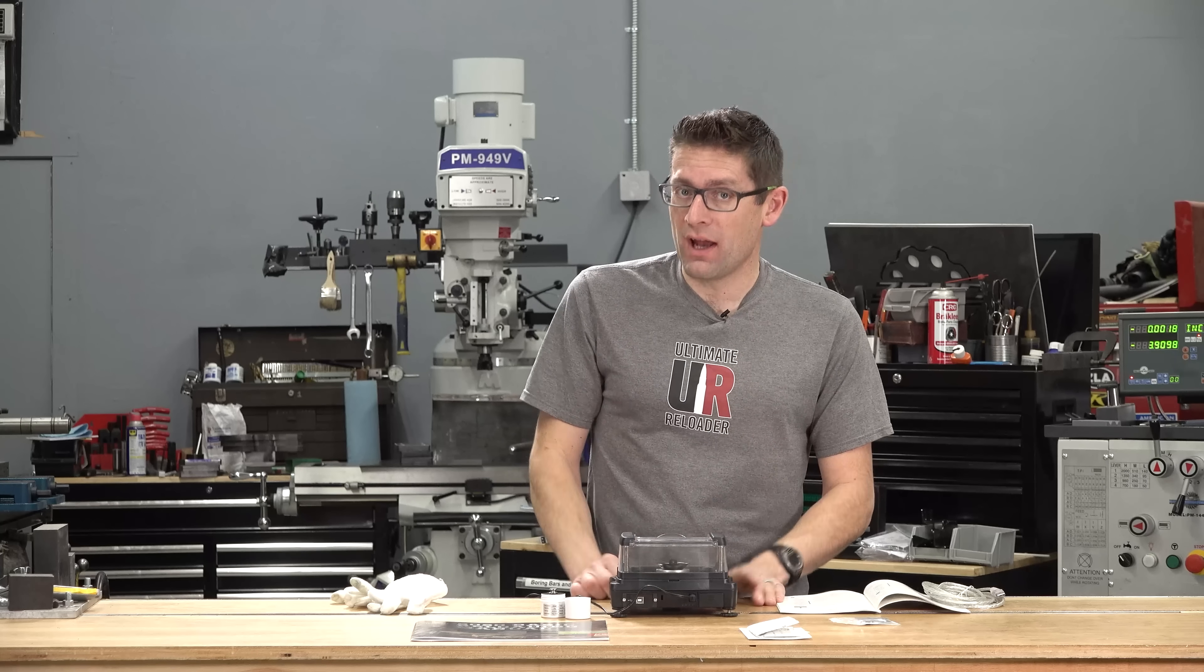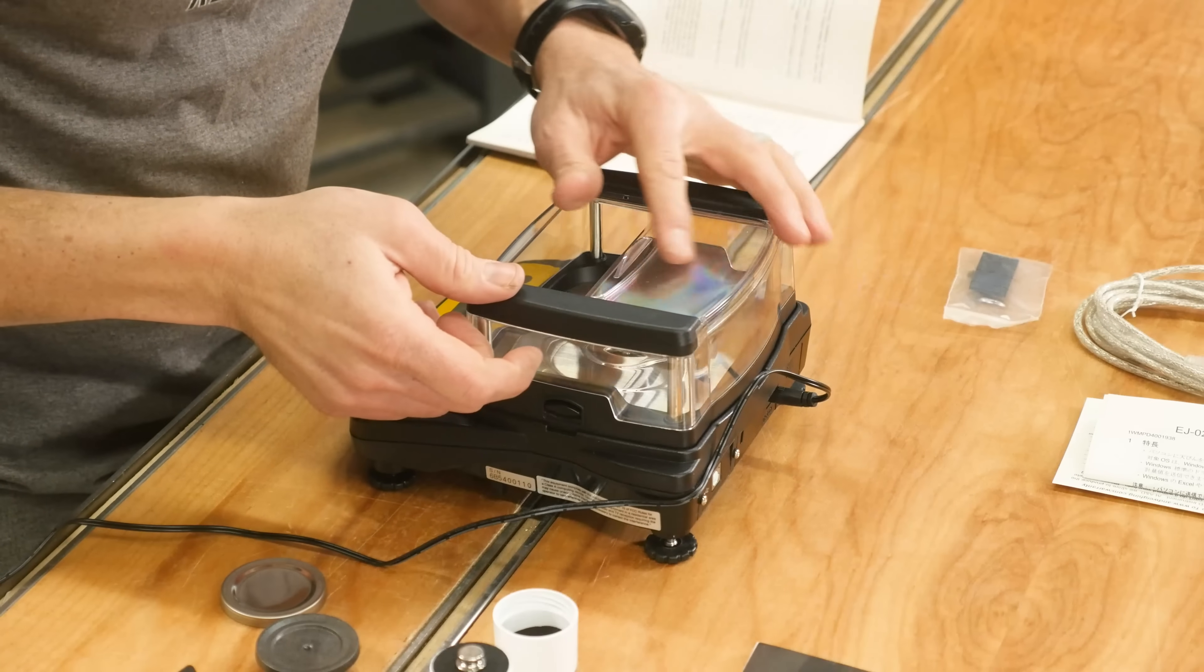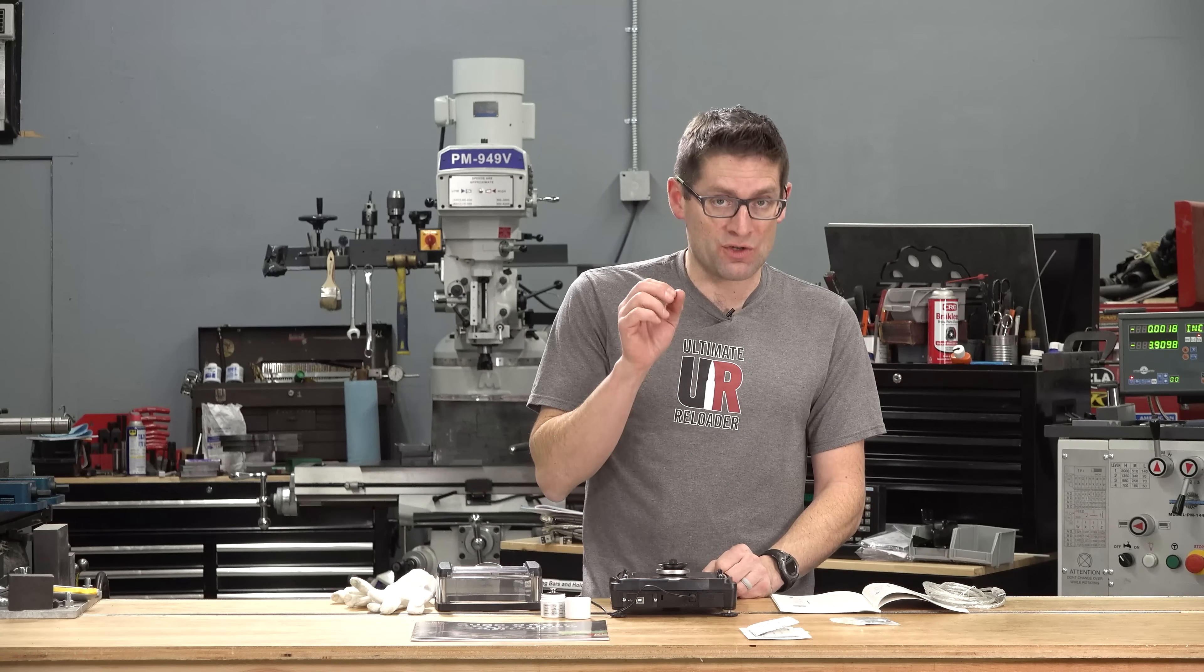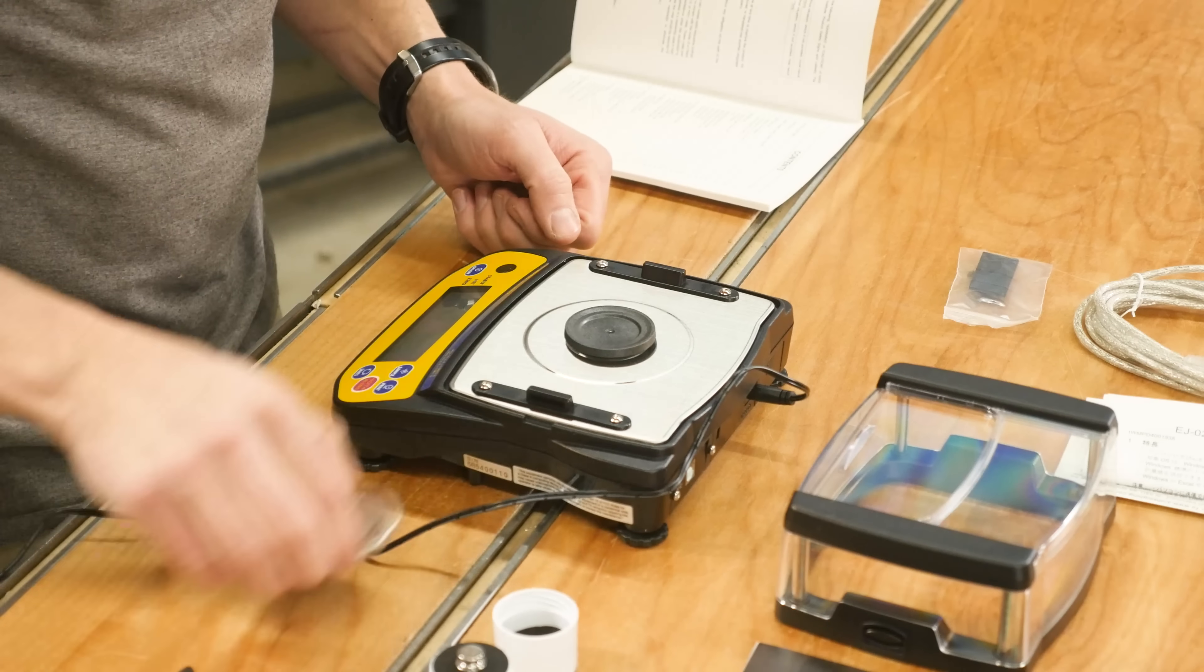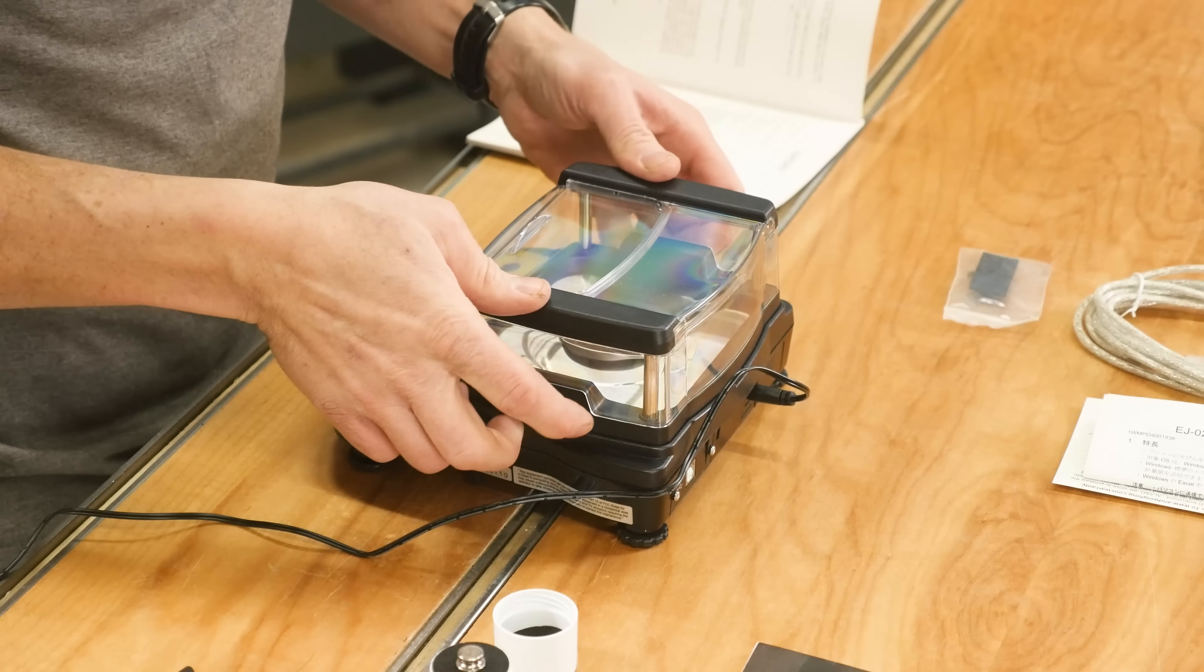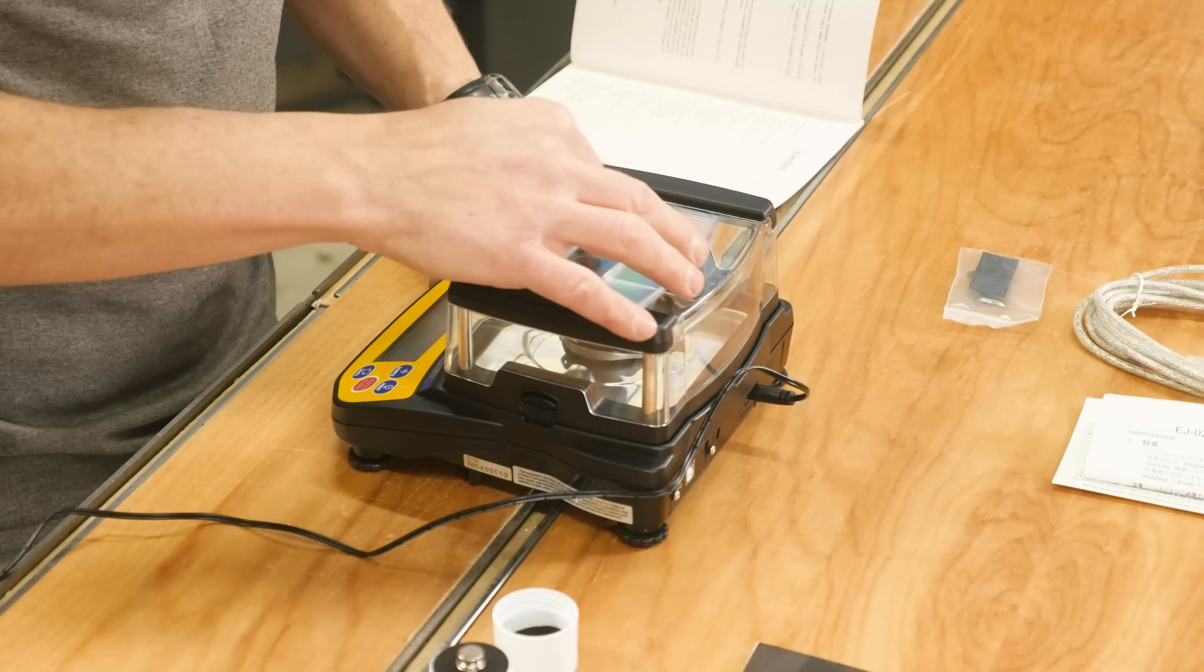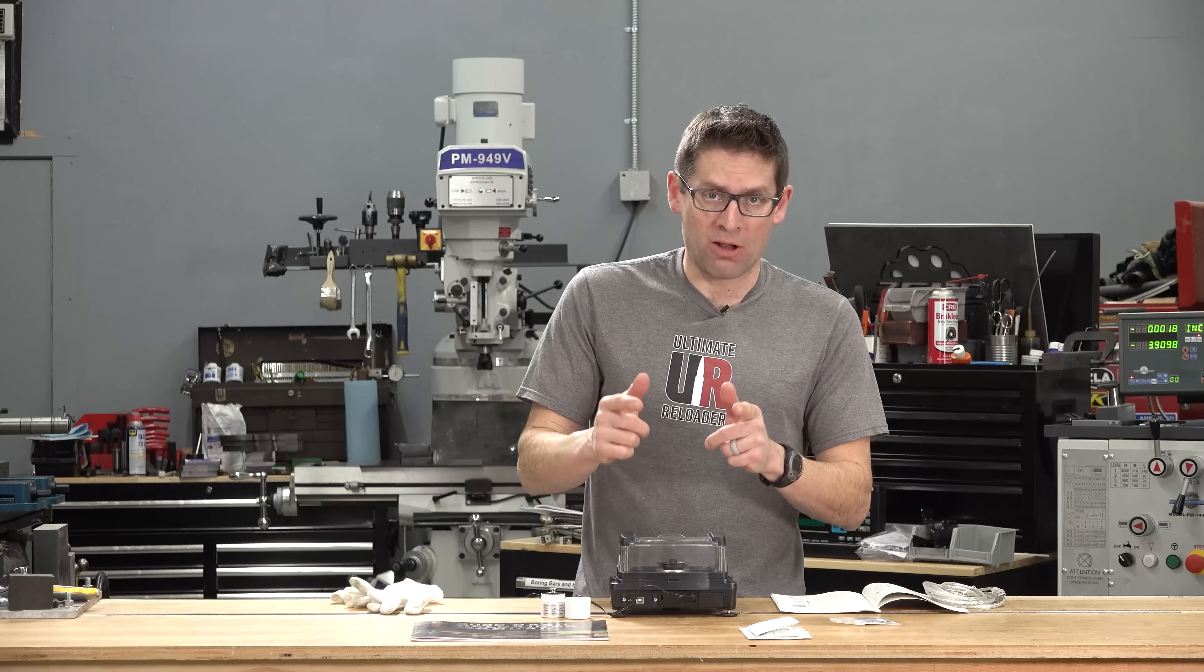In terms of setup, there's really not much to do. This particular scale has a sliding door on the top of the windscreen. If you lift up on these little levers on the side, you can completely remove the windscreen, which is great. You're going to take the plastic platen, put it on the scale sensor, then take the platen cover, which is metal, put it over the top of that, put your windscreen back on, and then you can put the pan on the platen if you so desire. Plug it in to AC power, turn the unit on, and wait about a half an hour before you calibrate the unit.